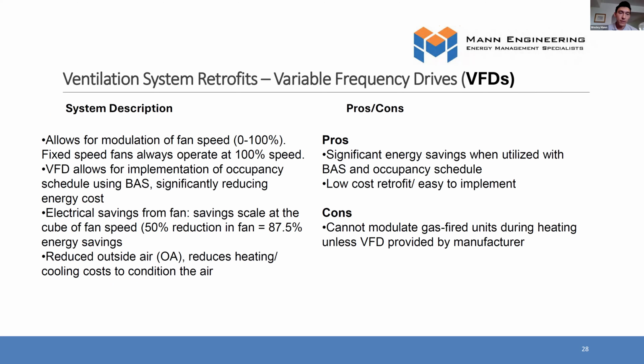Yeah, perfect. If you're going with a glycol coil retrofit, it's a great time to add a variable frequency drive to the unit. Now, when you're adding a variable frequency drive to a gas-fired unit, there are a lot of complications. If it's a single-stage gas-fired unit, typically you can't modulate the fan speed. You might have to retrofit the burner for a modulating or two-stage burner, because on a fixed, single-stage gas-fired unit, if you reduce the fan speed too much, that coil is going to get hot spots and destroy itself. So you typically can't do that. But if you're going with a hydronic, glycol coil system, no issue. You can modulate the fan speed.